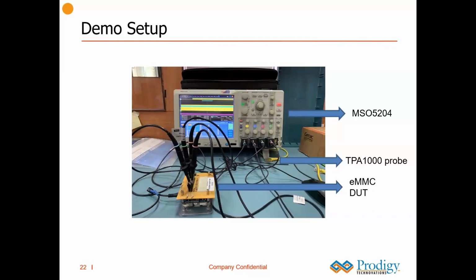Now, in order to reduce those ringings, we need to use a very short ground lead. Tektronix and other test and measurement vendors provide small lead wire, which will enable you to connect to the ground point, and make sure that it is also very short. This is a simple setup I'm showing you here, of how it needs to be connected to the device under test to make sure that you are making a reliable measurement.